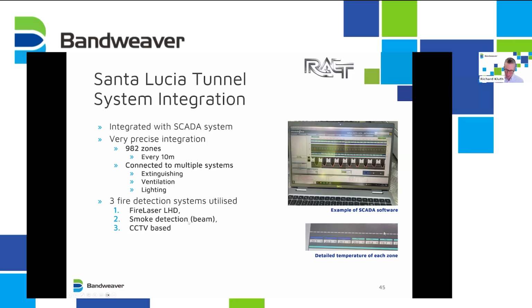We weren't the only fire detection system on site. They also used smoke detection, beam-based, and CCTV flame detection. But we were the only ones connected to the fire extinguishing system, because they had sprinkler heads every 10 meters, and they wanted that level of accuracy so they could really pinpoint the suppression.